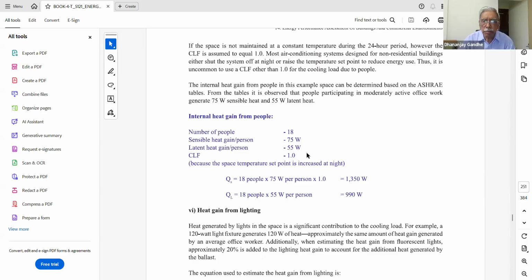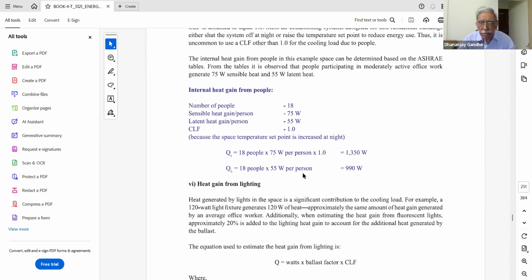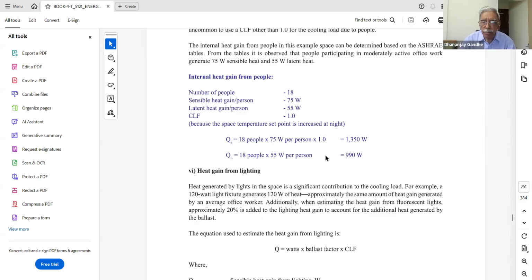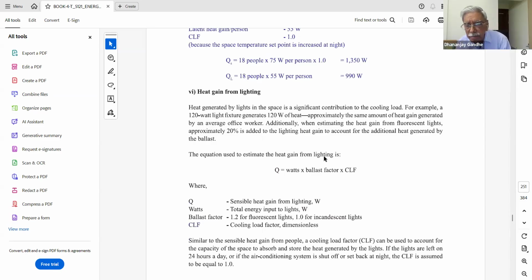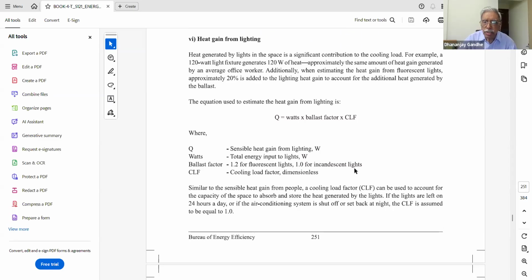These are standard figures which are considered for the calculation. Okay. So heat gain from the people is calculated here, depending on the number of people working in that area, and the CLF is taken as 1, or here there is a standard method. You can calculate the heat gain from the people. Similarly, heat gain from the lighting depends on the total wattage of the lamps. You can take the figures from the actual wattage of the lamps installed. So the exact total wattage of the lamps which is installed, multiplied by, assuming that these are fluorescent lamps, a ballast factor of 1.2. CLF is the cooling load factor, which is usually taken as 1.